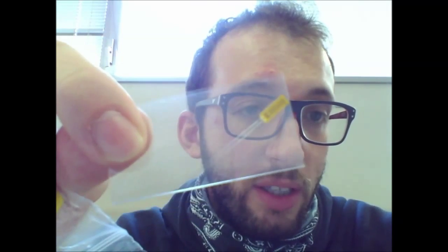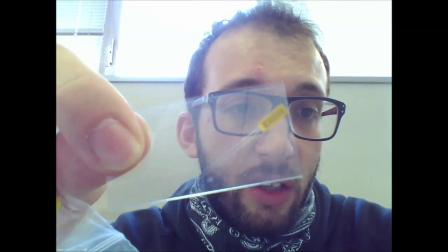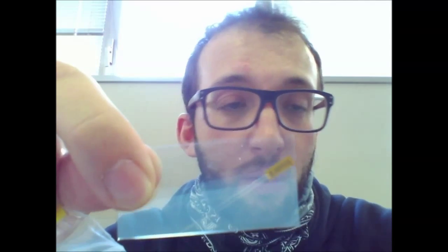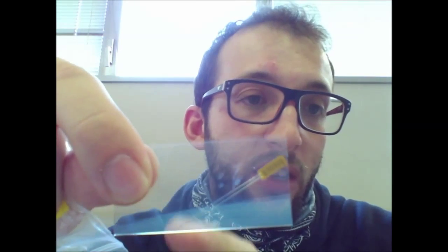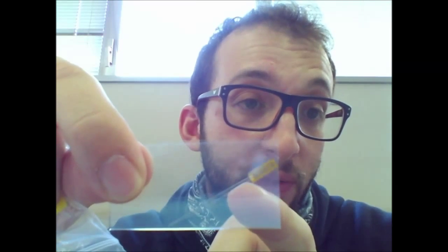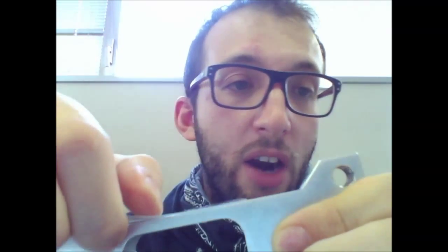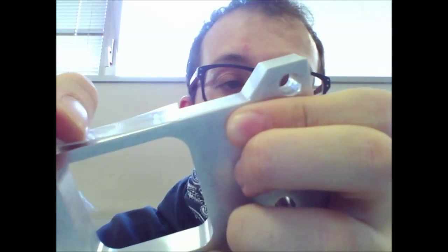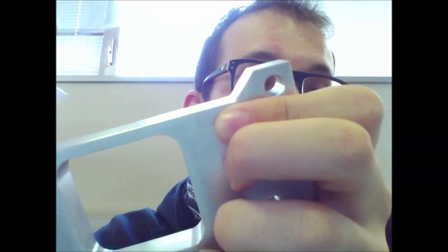However, strain gauges are designed to sense strains in a particular way. In normal conditions, they have a fixed value of resistance. In all load cells, extensimeters are glued in those zones where you have stress concentration. So they change their resistance due to strains.